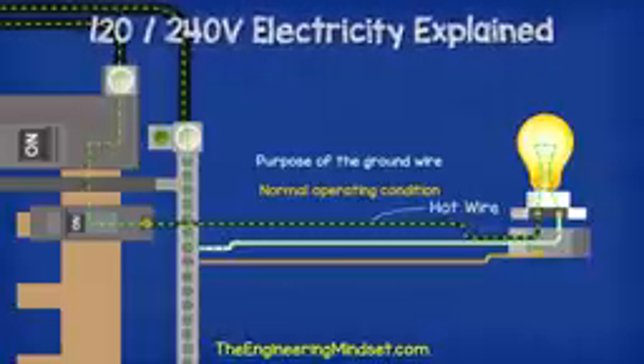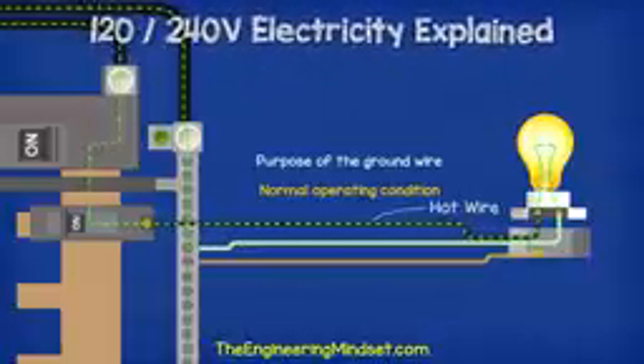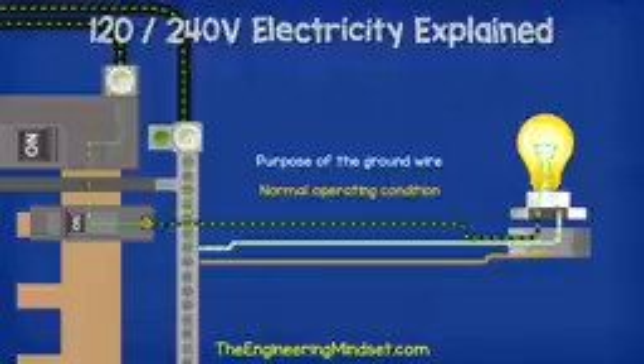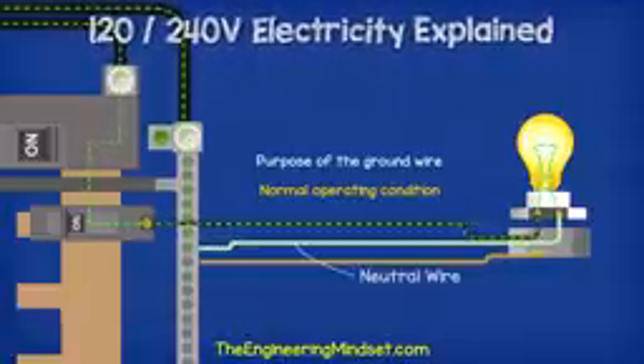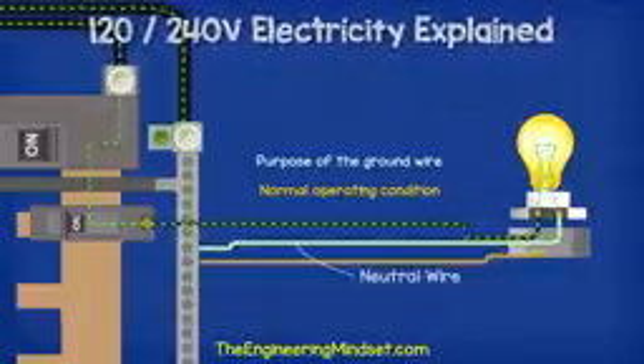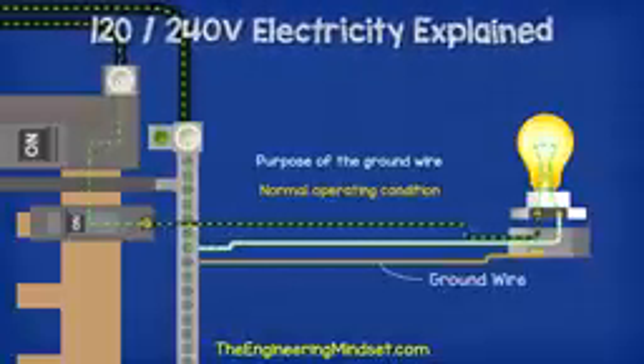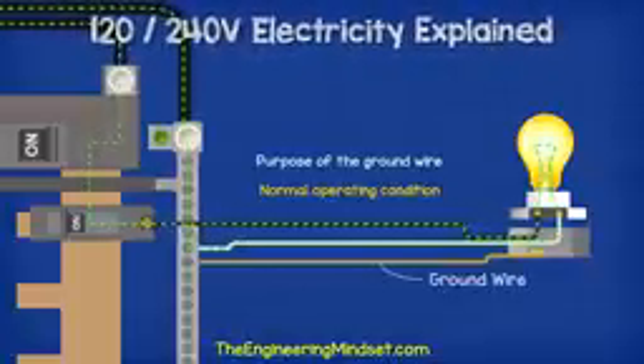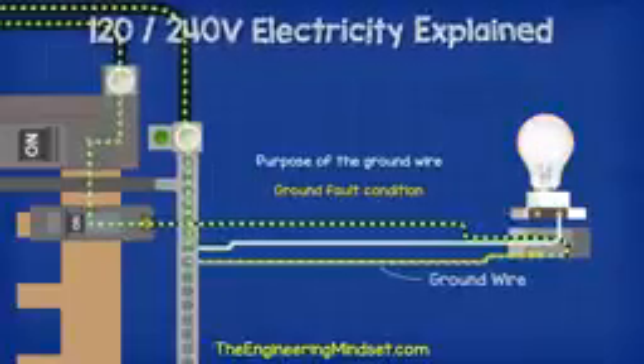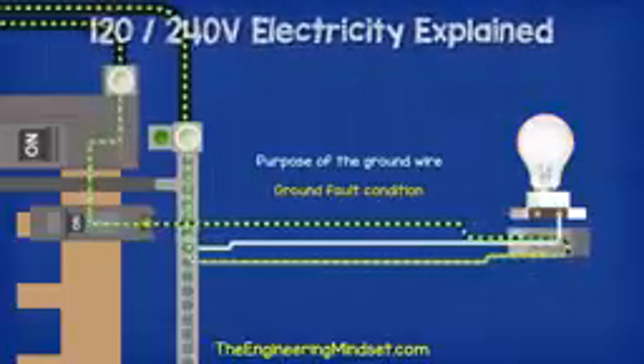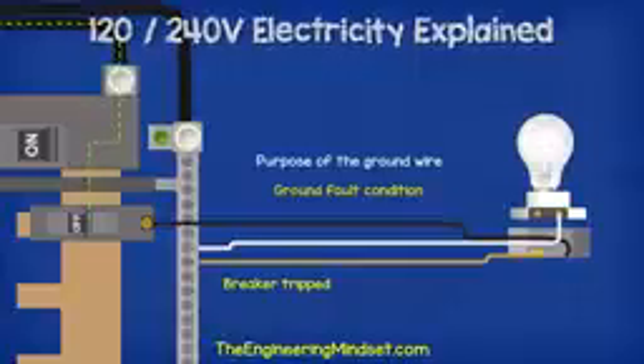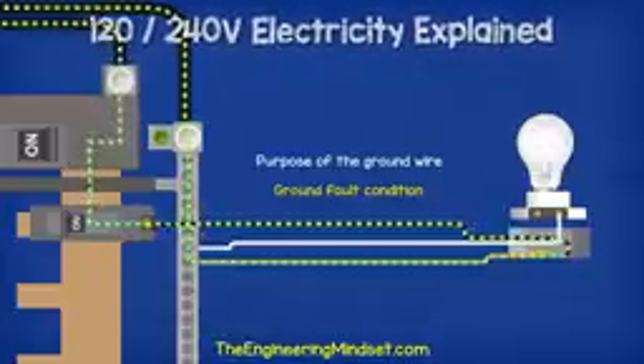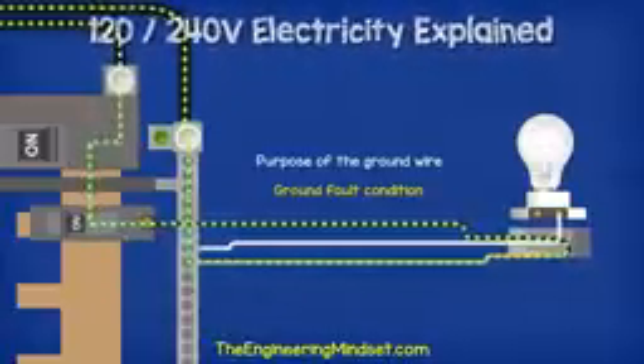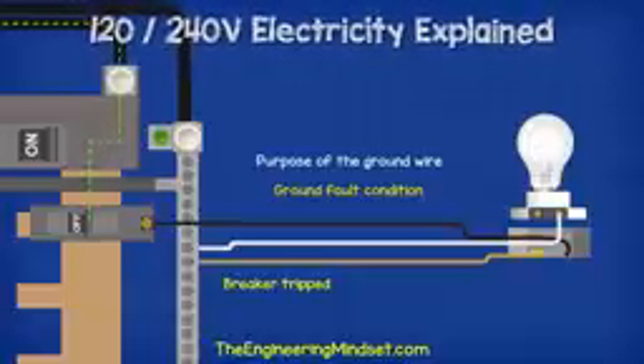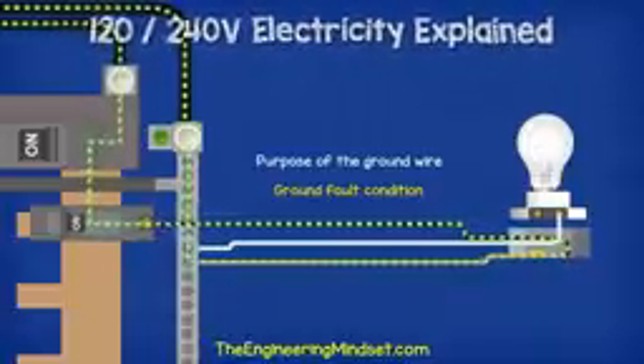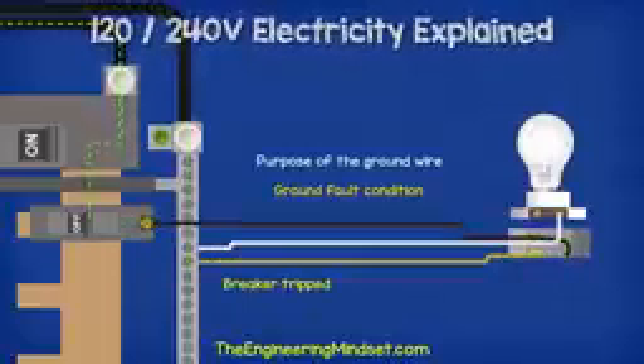The purpose of the hot wire is to carry the electrical current over to the light fitting. The purpose of the neutral wire is to carry the used electrical current back to the main panel and then back to the transformer. The purpose of the ground wire is to provide protection for a fault current. If, for example, the hot wire came loose and touched the metal casing of the light fitting, the ground wire provides a low resistance path back to the panel. Without this path, electricity could flow through you if you touch the metal box. As the current flows through the ground wire, it will increase the current and that will trip the breaker automatically.